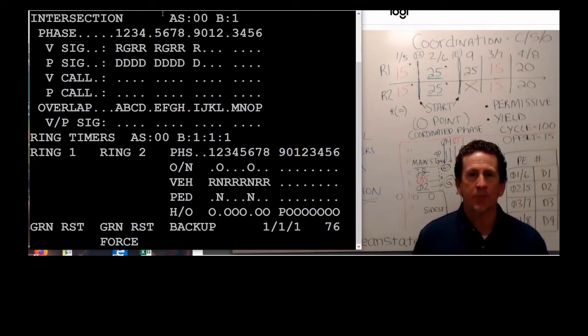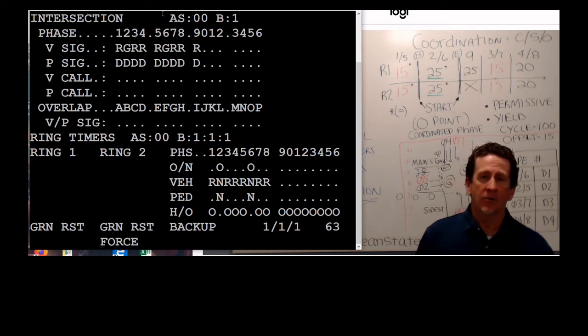Because when somebody hits a push button, the C should come on and the C should go off. If I have a constant C over there, that means I have a stuck button. For the older ones, you have a stuck button. For the APS buttons, you probably have either a bad button or a wiring issue that's grounding it true all the time, so that's staying on.